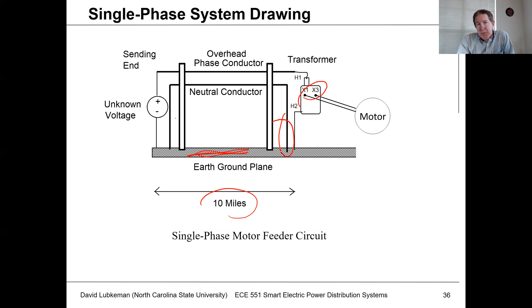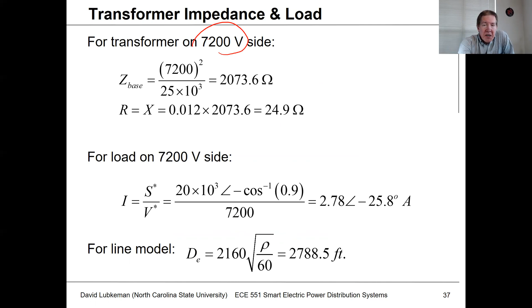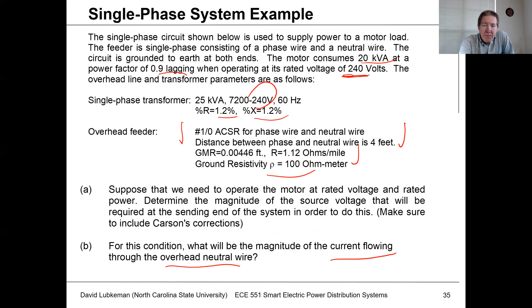So even if I had a transformer value in per unit, the program would actually convert that to a set of impedances in ohms. So in order to do that, I'm going to get everything on the 7200 volt side of the circuit. So basically, I've got a 7200 volt nominal source, and I'm going to get everything worked on this side of the circuit. This is the 7200 volt side. To do that, I'm going to need the base impedance. The base impedance is voltage squared over the power rating. V squared over 25 kVA is 2073 ohms. I would take the resistance in per unit multiplied by the base, and these are in terms of actual ohms. Again, this is on the 7200 volt side of that transformer, so I'm referring all the transformer impedances to that side.